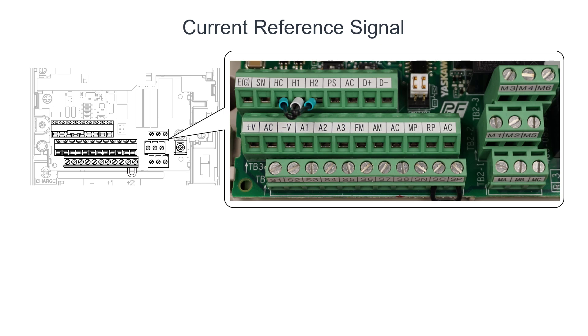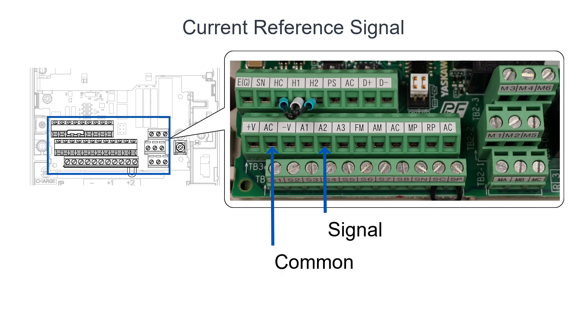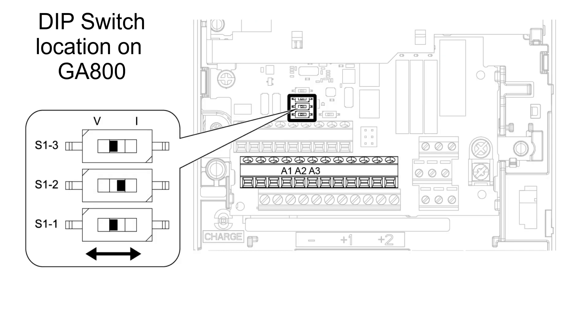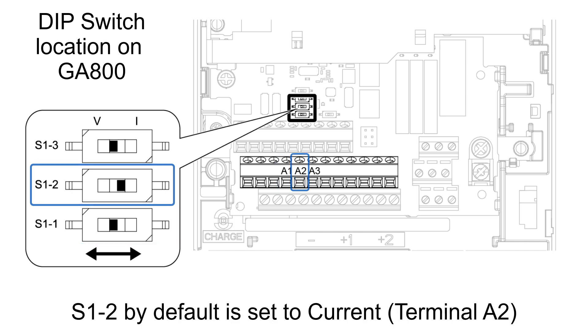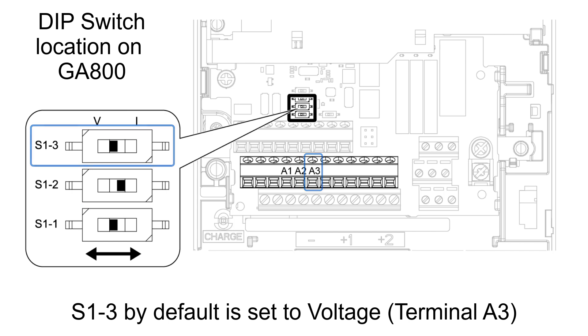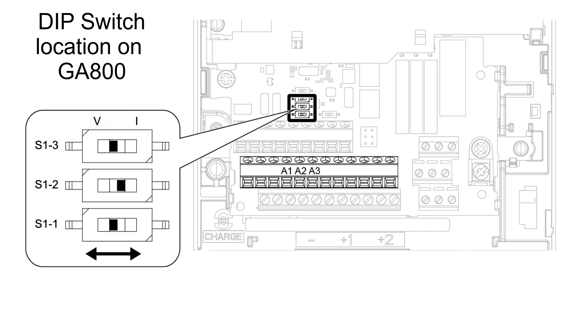If the reference signal uses current, check the wiring to verify it is correct — make sure the signal wire connects to A2 and the common to AC. Second, check the DIP switches on the drive control board. S1-1 by default is voltage for terminal A1. S1-2 by default is current for terminal A2. S1-3 by default is voltage for terminal A3. Once you have verified the DIP switch settings and wiring, try running the motor again.